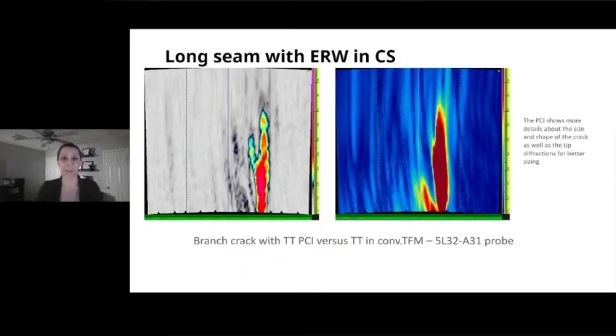Another example here for long seam ERW in carbon steel as well. Here, it's a branch crack using TT. This is the conventional TFM and the phase coherence. Again, it shows a bit more details about the size and the shape also of the crack and the tip diffractions for a better sizing.